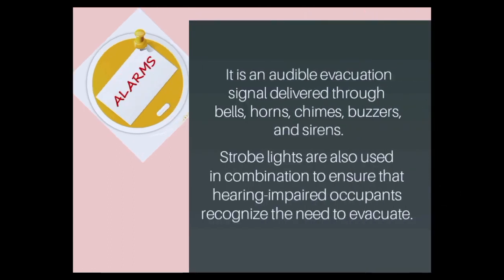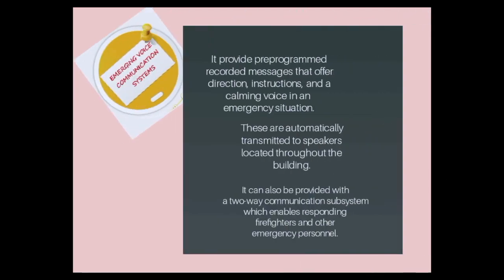Alarms. It is an audible evacuation signal delivered through bells, horns, chimes, buzzers, and sirens. Strobe lights are used in combination to ensure that hearing-impaired occupants recognize the need to evacuate. Emerging voice communication systems provide pre-programmed recorded messages that offer direction, instructions, and a calming voice in an emergency situation. These are automatically transmitted to speakers located throughout the building. It can also be provided with a two-way communication subsystem which enables responding firefighters and other emergency personnel.